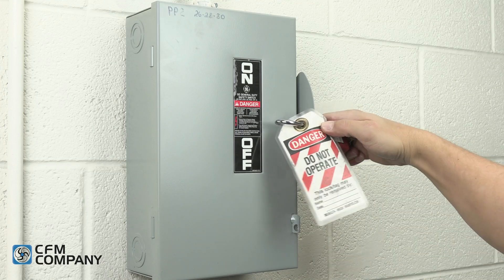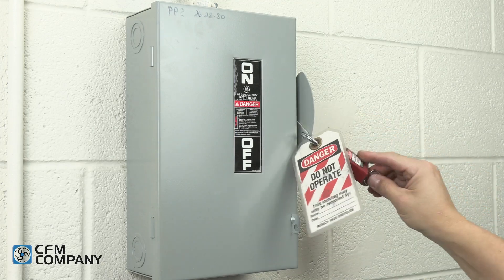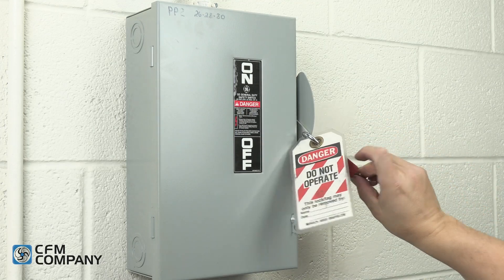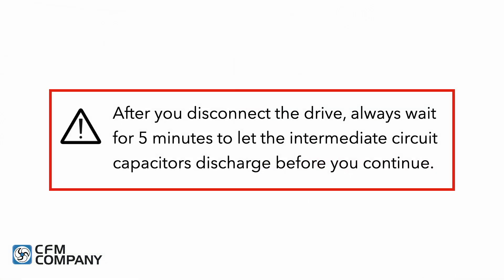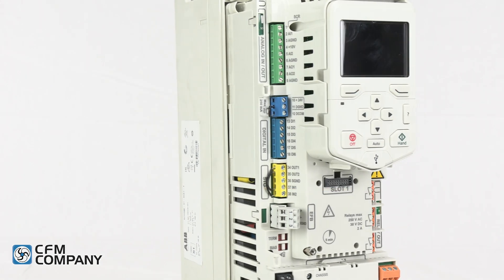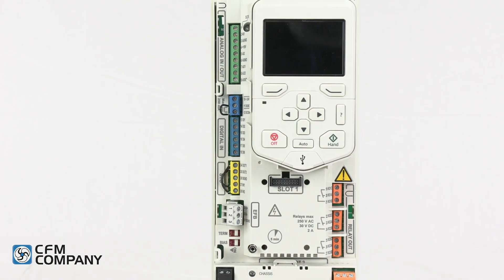Lock and tag out the circuit disconnect and make sure that reconnection is not possible. Always wait 5 minutes to let the intermediate circuit capacitors discharge before you continue. Remove the front cover to expose the control terminals.